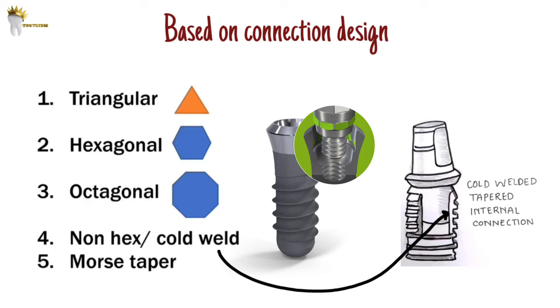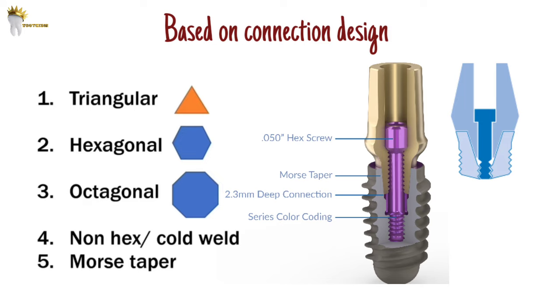In the cold weld design, no connection screw is needed — the abutment gets firmly engaged and cold welded into the implant connection. It is claimed that this connection forms a tight seal at the implant-abutment connection interface and prevents microbial growth. Another type is the Morse taper connection, which is a combination of both hexed and non-hexed connections. It has the hex in the deepest half of the internal connection for anti-rotational feature, while the smooth non-hexed surface in the crestal half makes a tight seal to prevent bacterial growth.